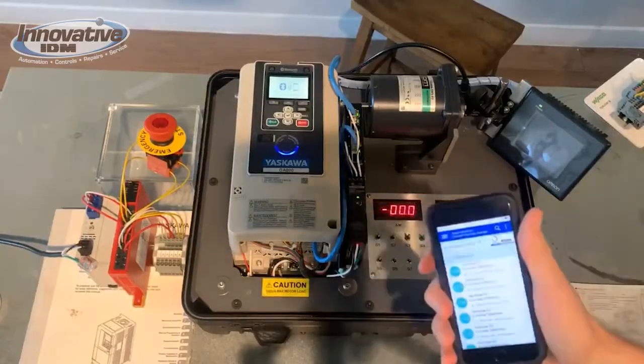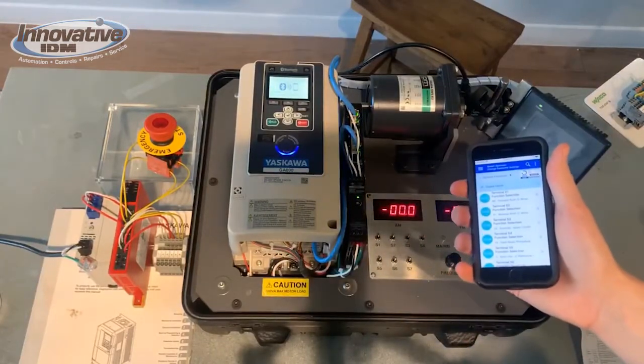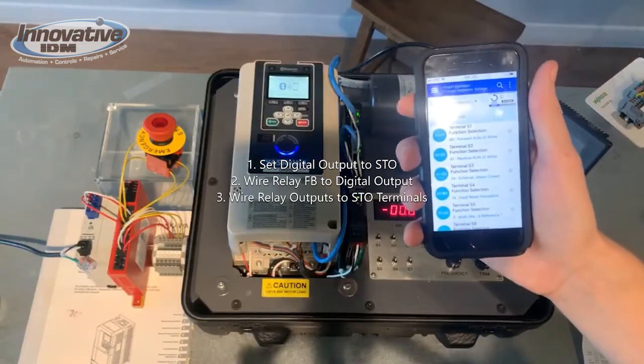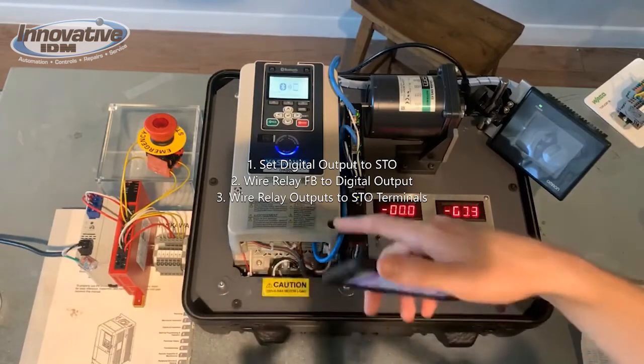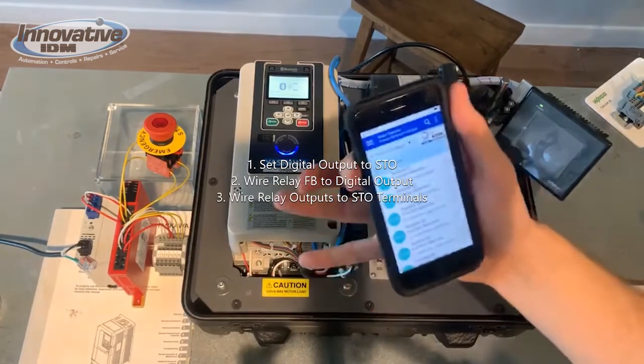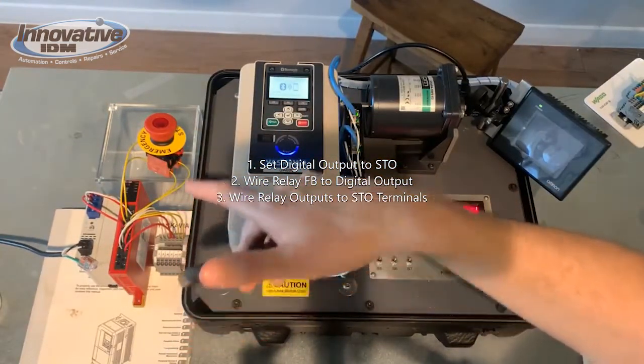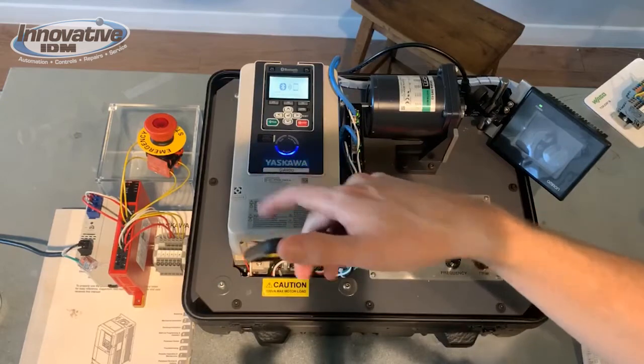There are three steps for setting up Safe Torque Off with this drive. The first is setting our programmable outputs to Safe Torque Off. The second is wiring our feedback from our safety relay into those STO inputs in our GA800 drive.